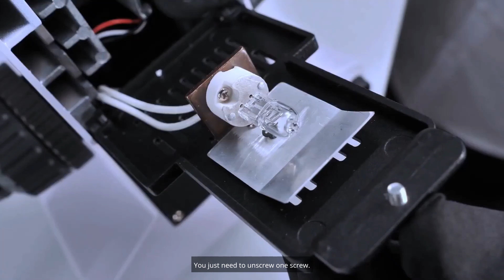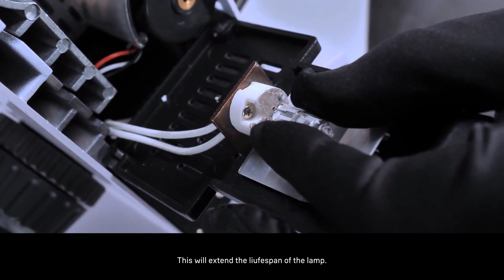Changing the lamp is very simple. You just need to unscrew 1 screw. When replacing the lamp, remember to use gloves or a cloth. This will extend the lifespan of the lamp. Halogen lamps of 12 volts and 30 watts have high brightness and are available in stores. If you need to replace a LED, we recommend consulting a specialist.